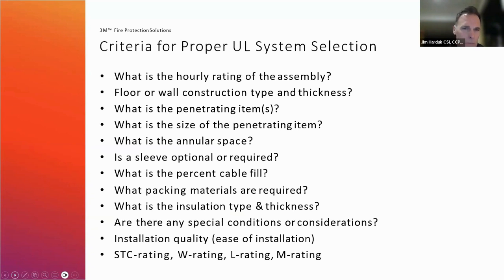There's some other items that might be required too, like, do we need a sleeve? Is there a sleeve in the wall assembly that we need to address? If we're dealing with groups of cables, we need to know the percent of cable fill. If we're dealing with insulated pipe, obviously we would need to know what type of insulation is being used and the thickness. So there are a couple common criteria that you need to identify in order to point yourself in the right direction for system selection. Next slide.